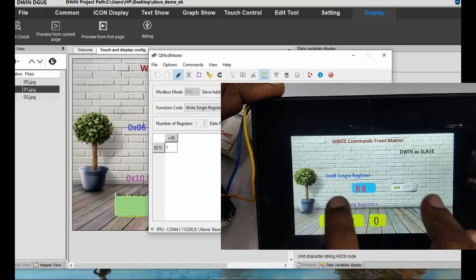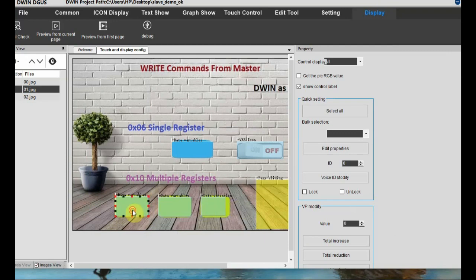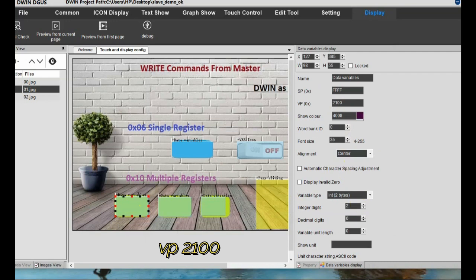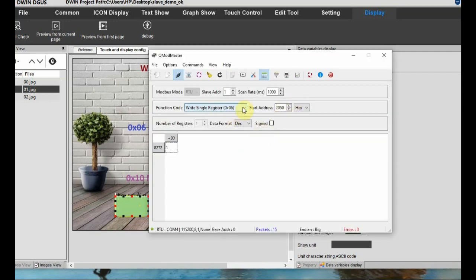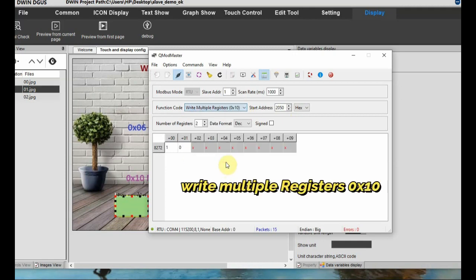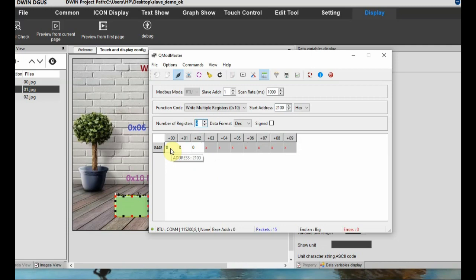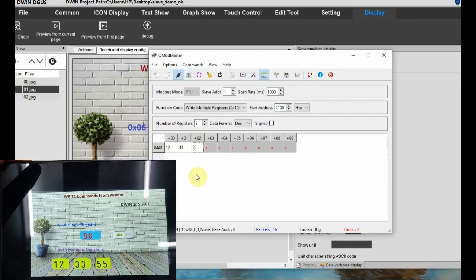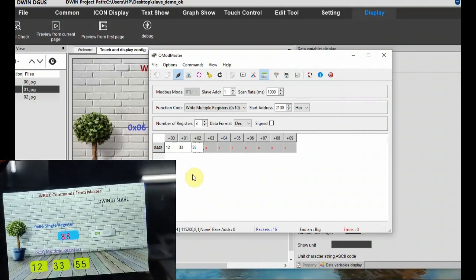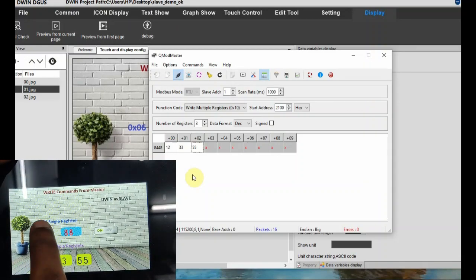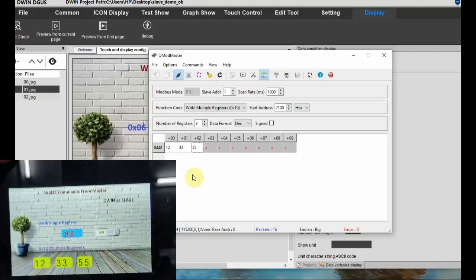For testing multiple registers we have three locations: VP 2100, 2101, and 2102 - three VP locations for data variables. Select the command as 0x10, write multiple registers, with start VP address 2100 and number of registers 3. Feed in the values in QMod Master for locations 2100, 2101, and 2102. Click Read/Write to execute - you can see the values being reflected in the DWIN slave. This is the 0x10 command for multiple values. Thank you for watching.